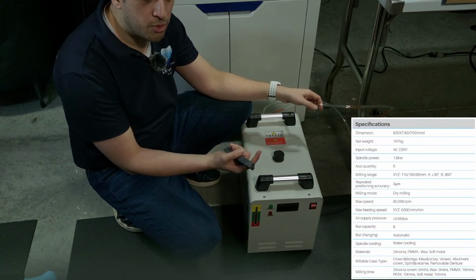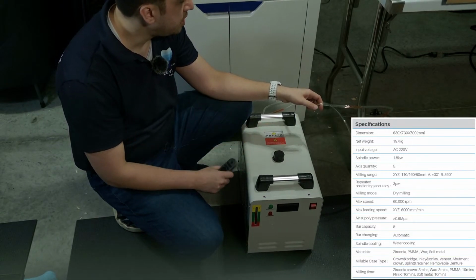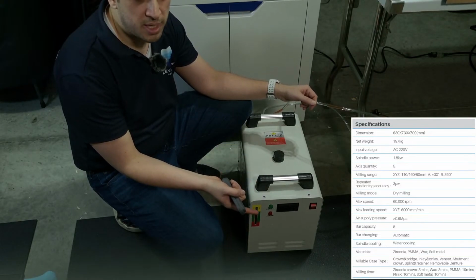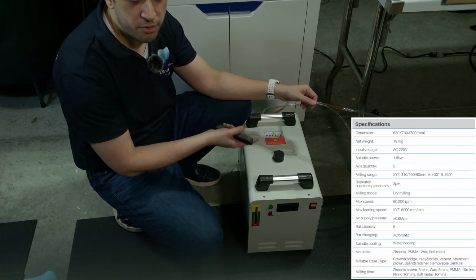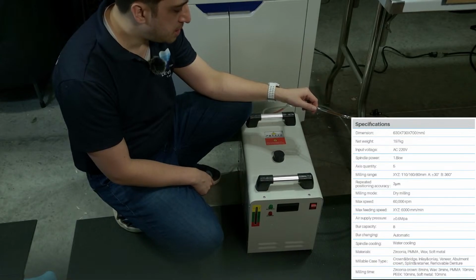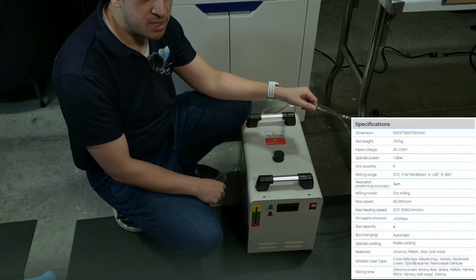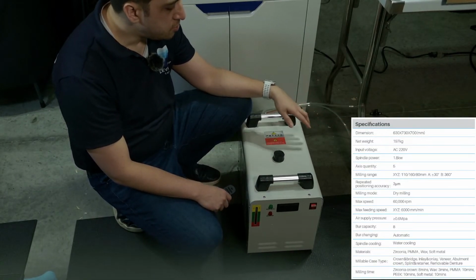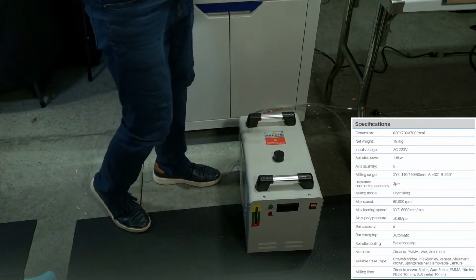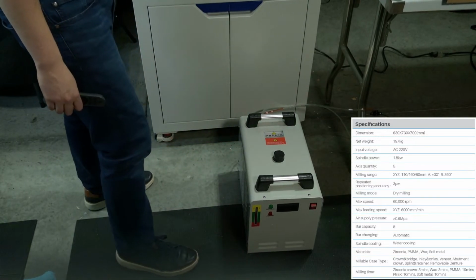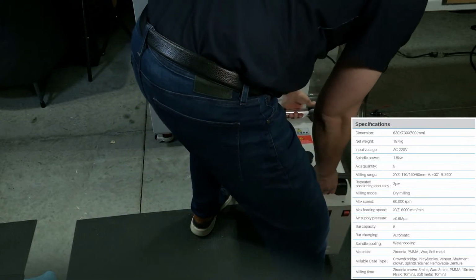The easy way to do that, you've got an in and an out, so you remove the out from the back of the machine. You basically put the hose in a bucket, let it pump all the fluid and coolant out and into the bucket. That essentially flushes the system. Then you can put new coolant in there and let everything run back up to the machine. So where does this hook up to inside of the machine?